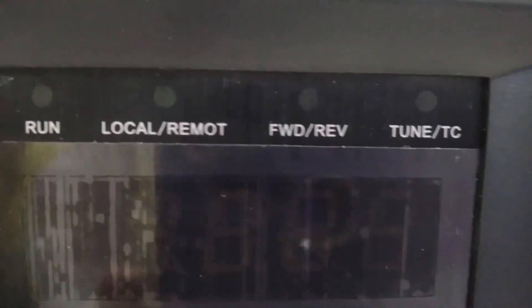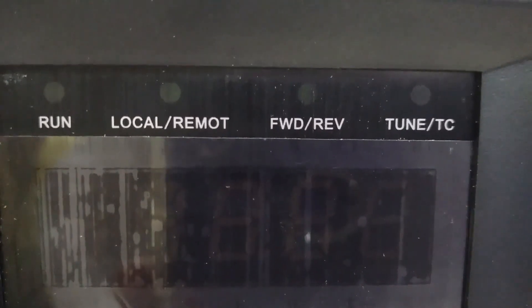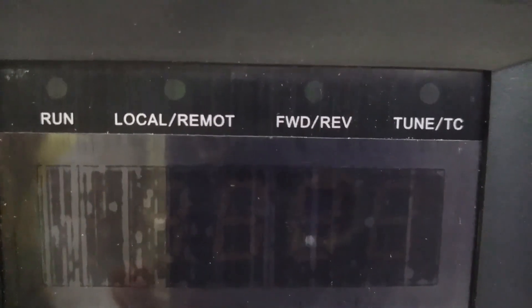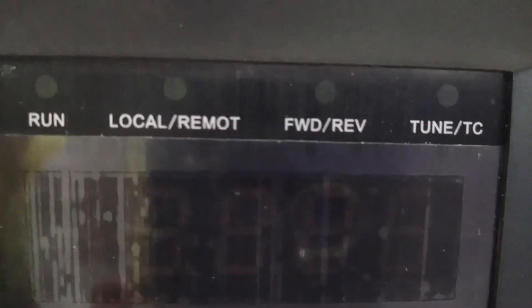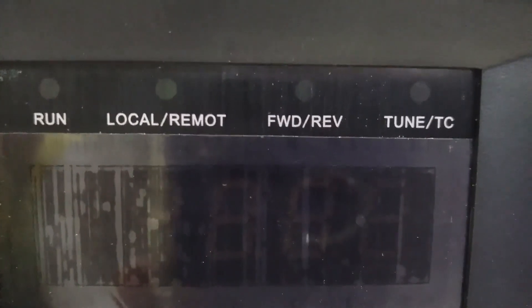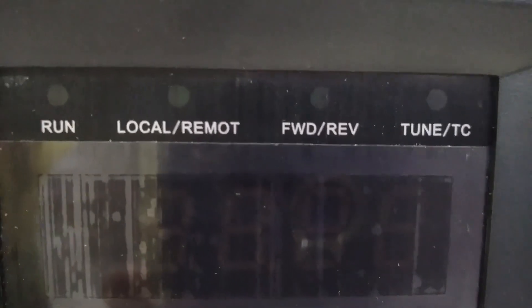At the right most, we have tune or TC LED indicator. TC means torque control. If tune or TC LED is on, the VFD is in torque control mode. If the LED is off, the VFD will operate in normal mode. If tune or TC LED blinks slowly during motor auto-tuning operation, however, if this LED blinks quickly, it is an indication of a VFD fault condition.